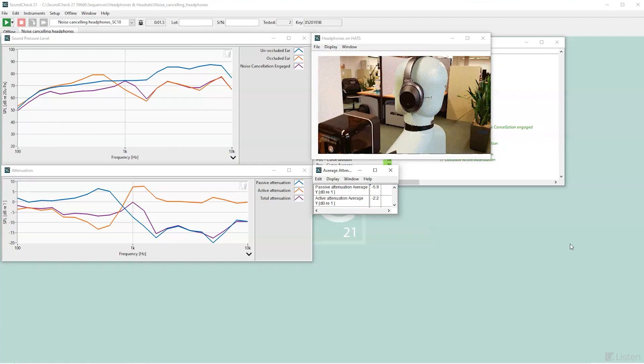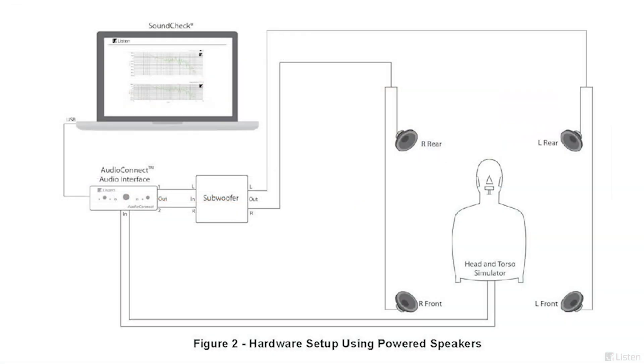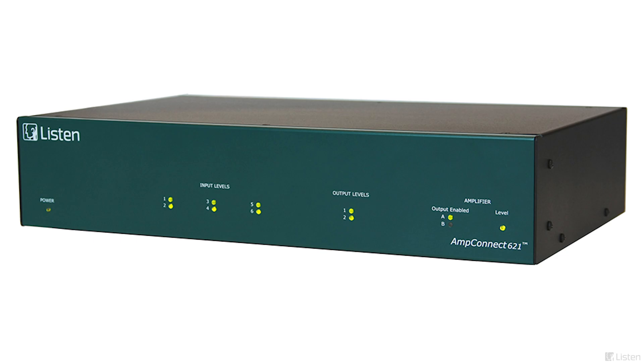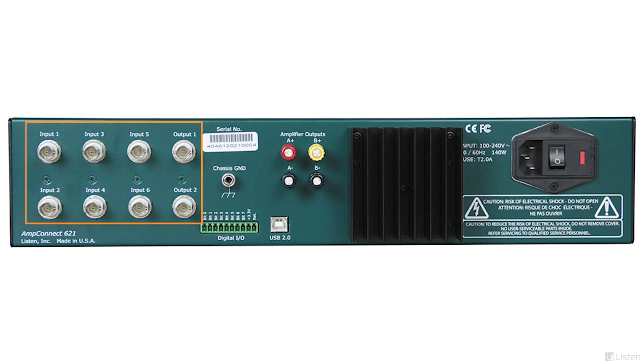This test can be modified to work with a diffuse multi-speaker configuration, and in an environment with two or more speakers, both ears can be measured at the same time. Our new AMP Connect 621 interface has six inputs and two outputs, so you can even measure both the left and right channels simultaneously while also generating stereo background noise.